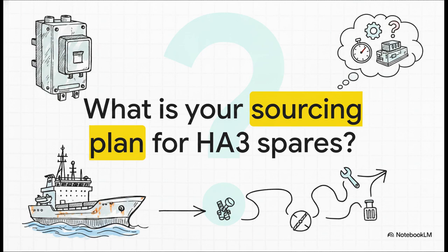Okay, let's anchor these technical specs to physical reality. Put yourself in the shoes of a commissioning engineer. Let's do a quick check: say you're on a 20-year-old platform supply vessel, and you've just been told, hey, we need spare poles for an HA3 breaker. What is your realistic sourcing plan here? Remember, you can't just call the factory and order brand new parts off the standard assembly line, because HA3 production ended a long time ago. So how exactly do you keep this vessel operating safely without causing massive downtime?